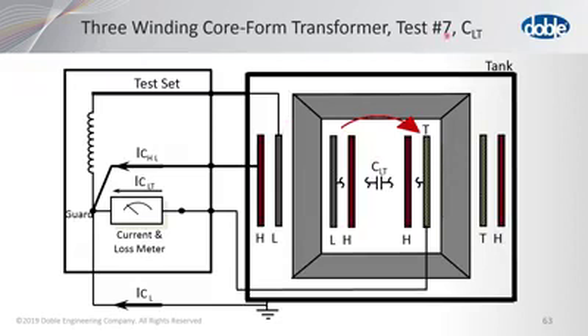In the test in question, number 7, the CLT test, we are energizing the low voltage winding and trying to get to the tertiary. Notice again that the high voltage winding in this case is guarding the two. So that's one reason you're getting a low current. Well, the other reason is, look at the distance. The current will go down because of the increased distance between the two windings. So there are two reasons why this current is very, very low: the shielding effect and also the distance.